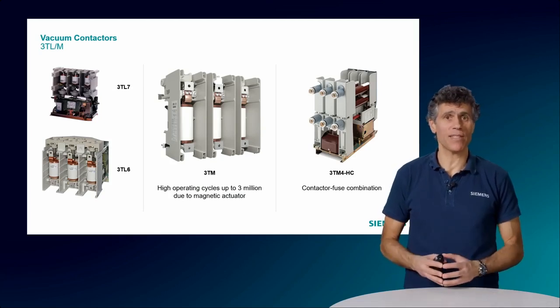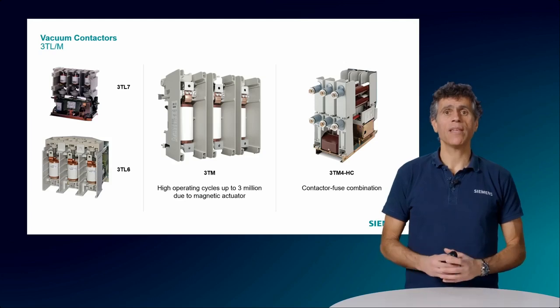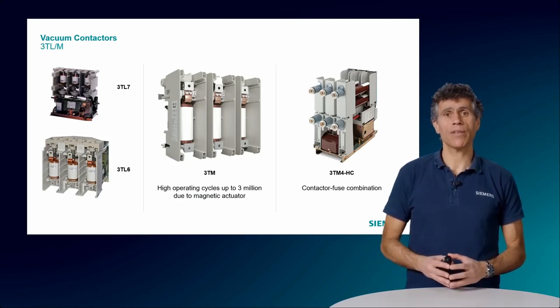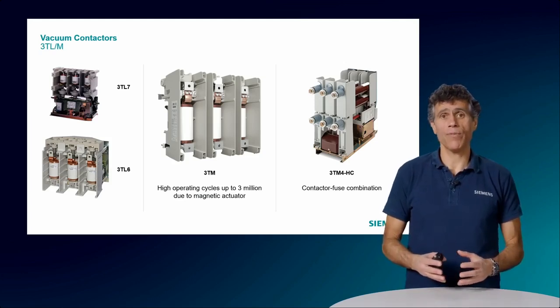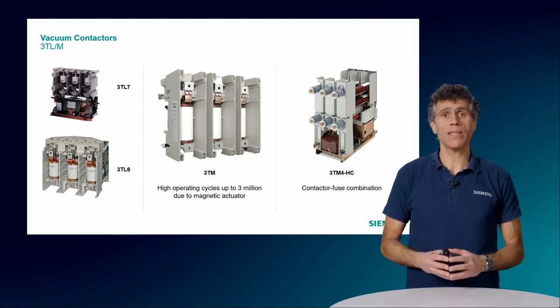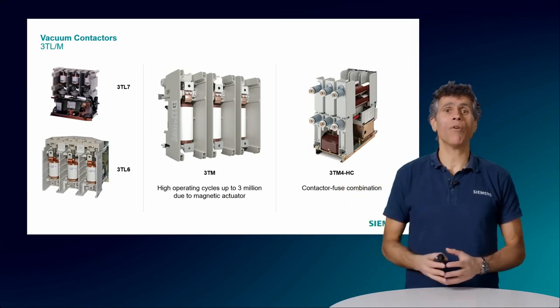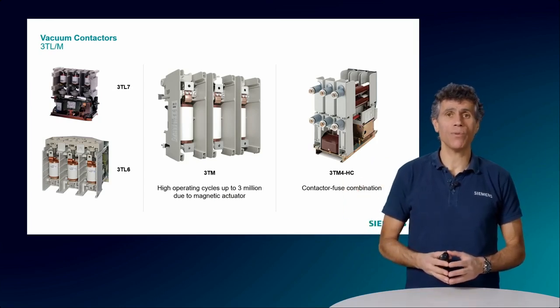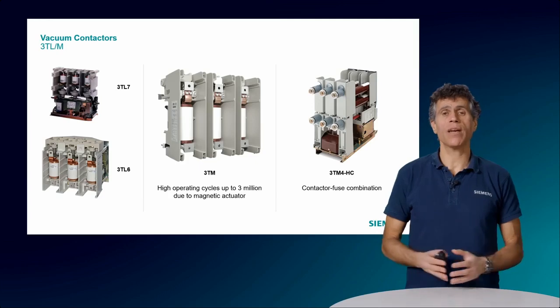Of course, the event of a short circuit current occurring must also be protected, even when using contactors, and this is why these devices must be protected by an upper circuit breaker or, more frequently, are used in combination with fuses, which are then used to break the high short circuit currents.